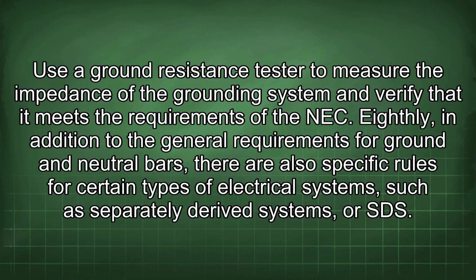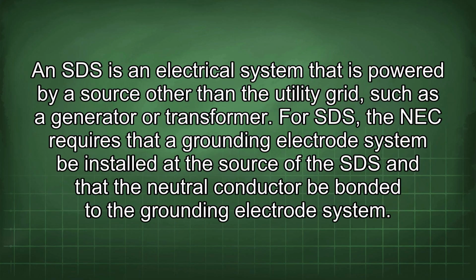Eighthly, in addition to the general requirements for ground and neutral bars, there are also specific rules for certain types of electrical systems, such as separately derived systems, or SDS. An SDS is an electrical system that is powered by a source other than the utility grid, such as a generator or transformer. For SDS, the NEC requires that a grounding electrode system be installed at the source of the SDS and that the neutral conductor be bonded to the grounding electrode system.